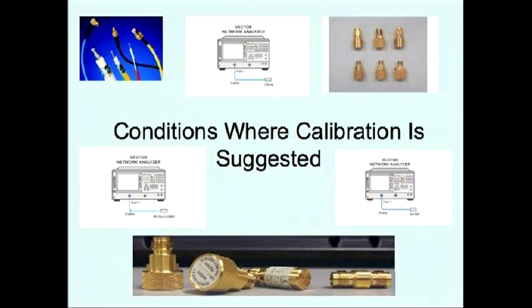Generally, you should calibrate for making a measurement under the following circumstances: You want the best accuracy possible. You are adapting to a different connector type or impedance. You are connecting a cable between the test device and an analyzer test port. You are measuring across a wide frequency span or an electrically long device. Or you are connecting an attenuator or other such device on the input or output of the test device.